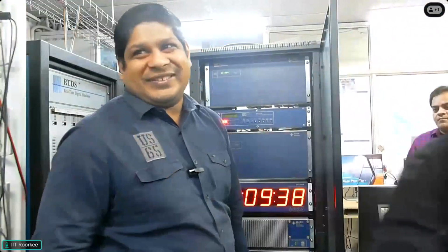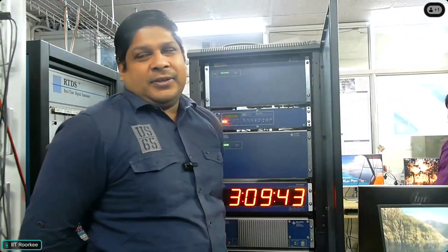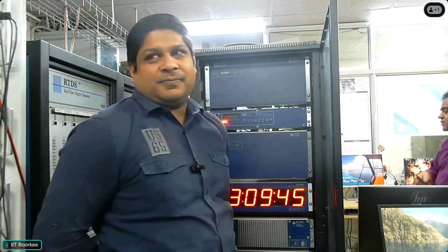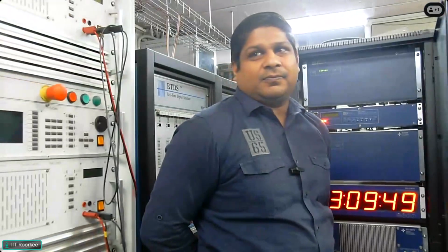With the newer technology, if you have merging units, what we have done is, out of the PMU, we have taken out the small part that takes the analog signal and converts it to a digital signal. The digitized values then go to another unit, whereas the PMU has everything together.